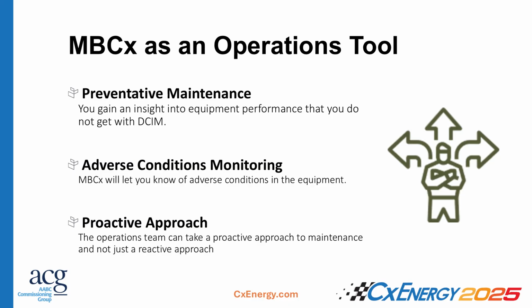As an operations tool for preventative maintenance, it's not just like having the BAS where chilled water pump 1 fails and you get an alarm. You could set it up as a commissioning provider so that if the power consumption on chilled water pump 1 goes from 7 kW up to 14, that gives you an early indicator that something's going on, and we can address that.